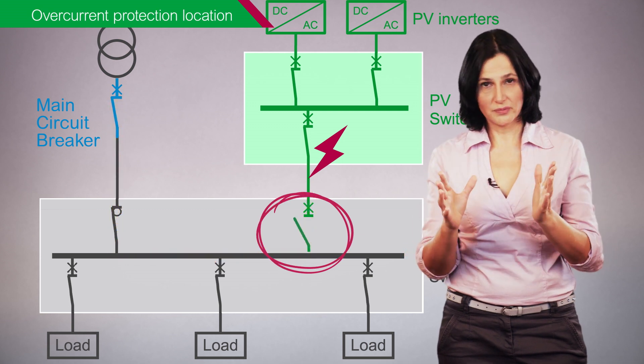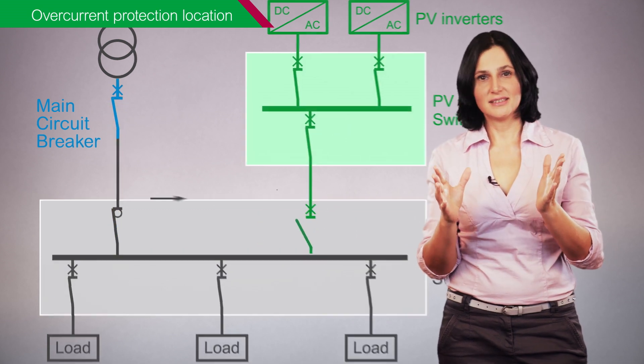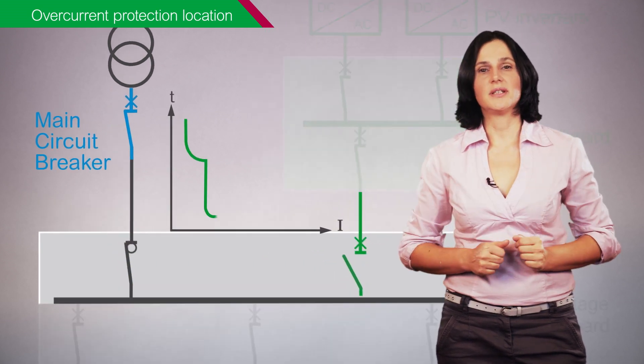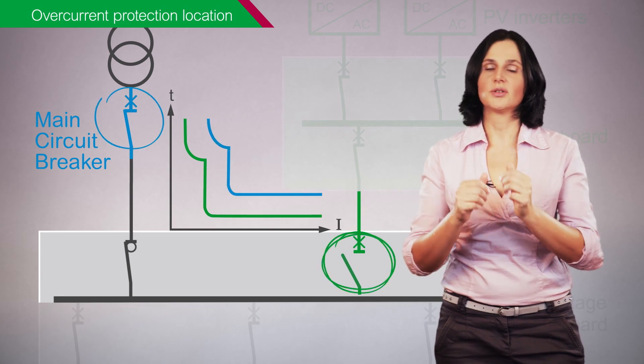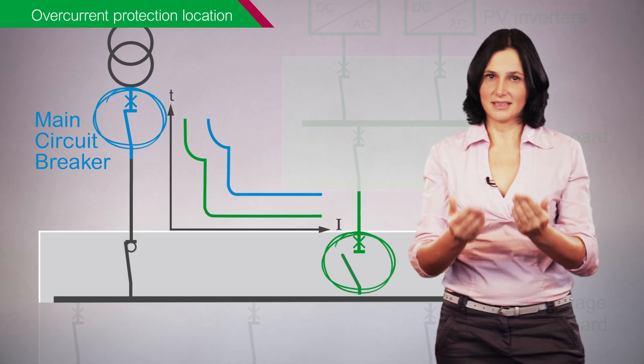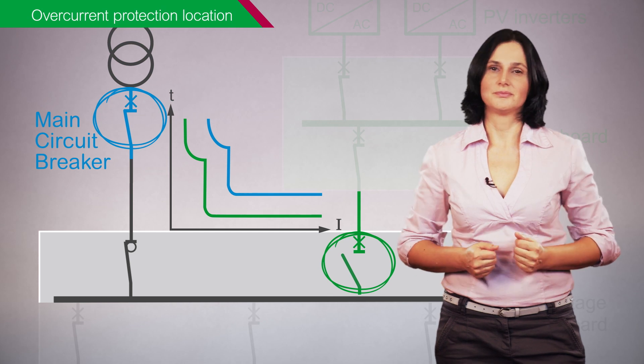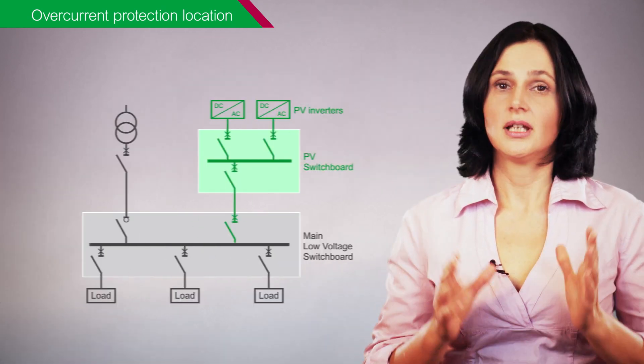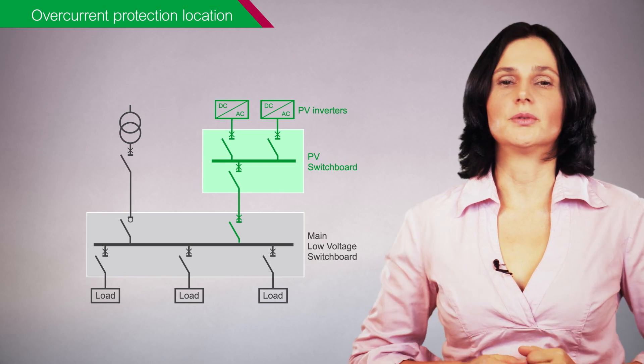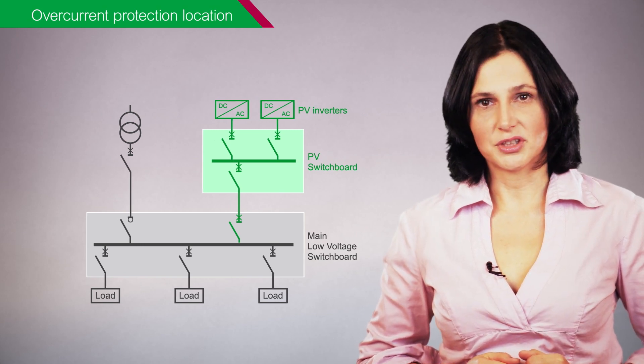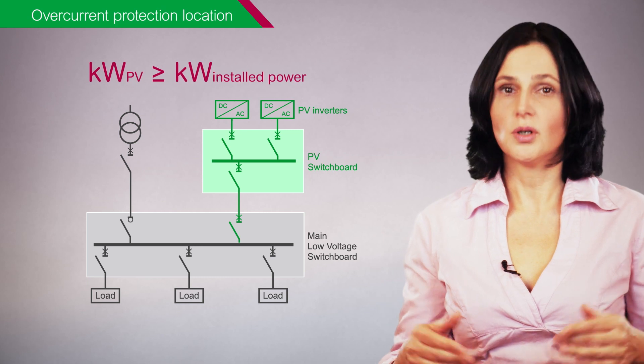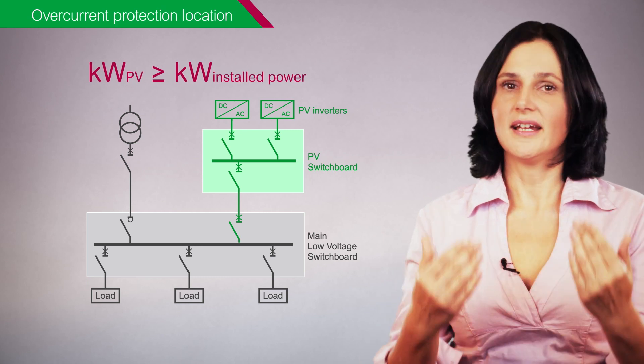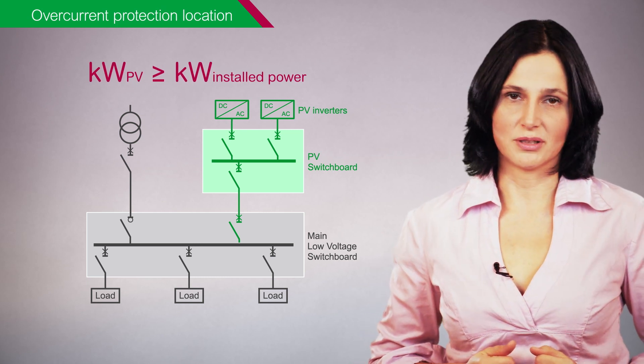To ensure things work properly, this overcurrent protection should be coordinated with the main circuit breaker to guarantee selectivity. This selectivity may not be so easy to achieve, in particular when the photovoltaic production capacity is equivalent to or higher than the building's installed power.